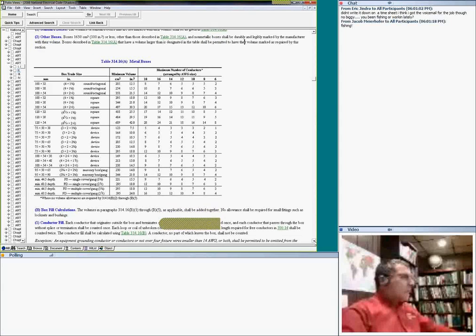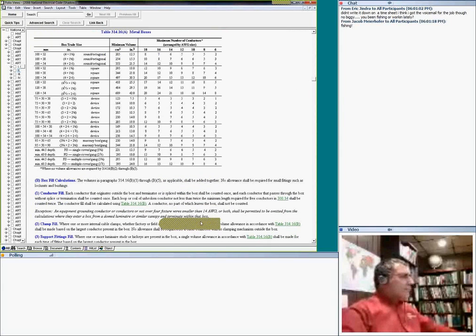All right, on to the table. If you use this table, it's very interesting. I assume that you have it, but I'm going to explain it as if you do not use it. Let's say, guys, I'm going to use a square box. You have to decide what type of box. I want to use a square box, the shallowest square box, which is 1 inch and a quarter. Of course, the square box gives you a volume of 18. How do we read it? 18 cubic inches.